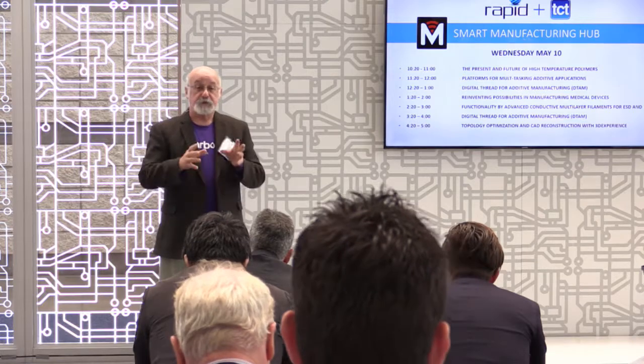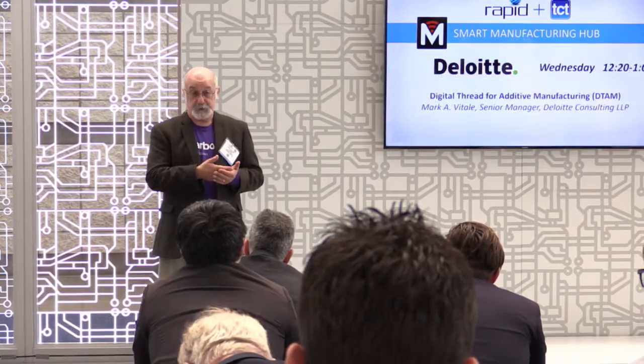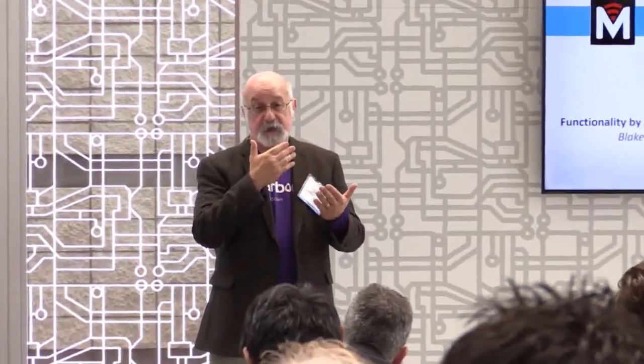If you're going to incorporate your machine into manufacture, ultimately the client is going to expect that you can provide them the kind of information they need to survive an FDA audit about their manufacturing process. If you're in the 510K or the exempt space, manufacturing is not something the FDA sees until there's a problem. And then they can come back and audit, so you should have the documentation and the quality systems in place. For a PMA device, it's all in, and you have to have that manufacturing data up front as part of the submission. But for 510K and for Class 1, the machine manufacturer or the resin developer really has to be there for their client when they are in trouble.